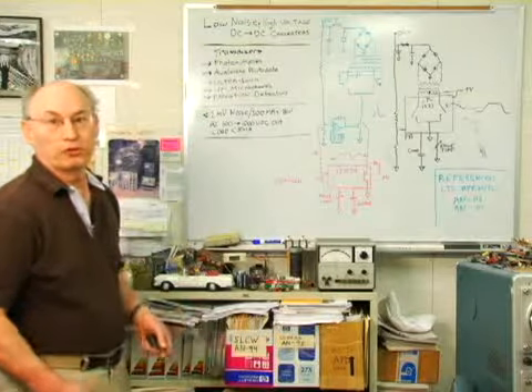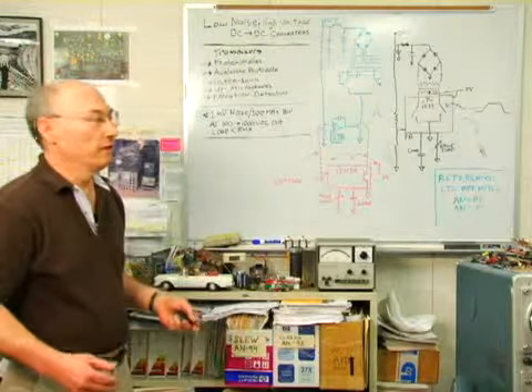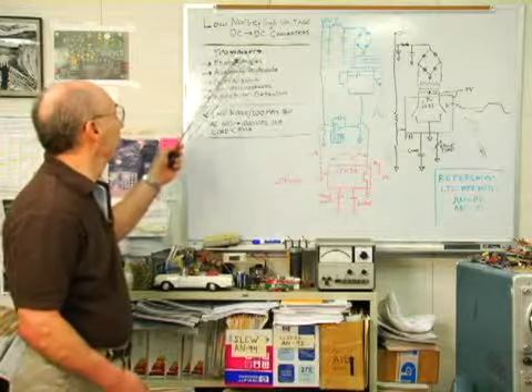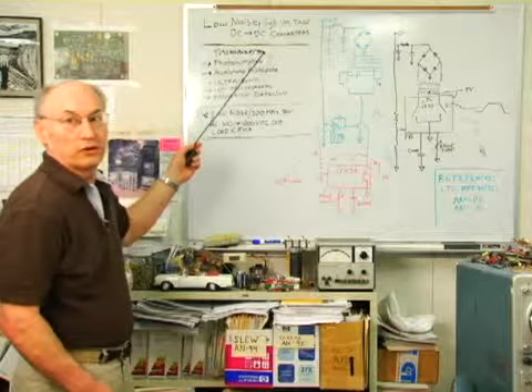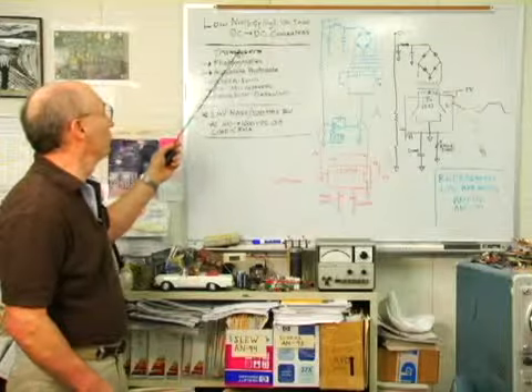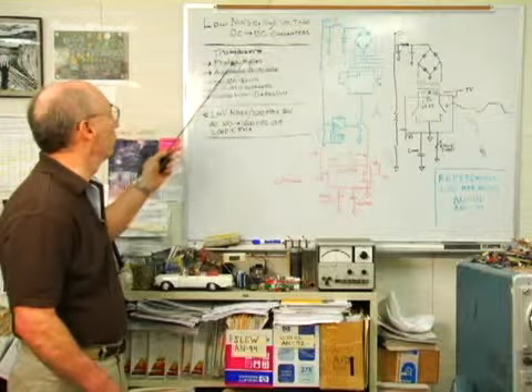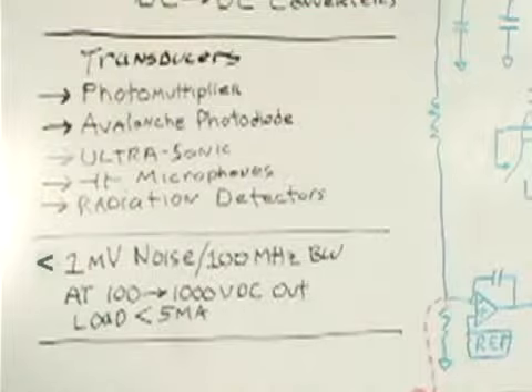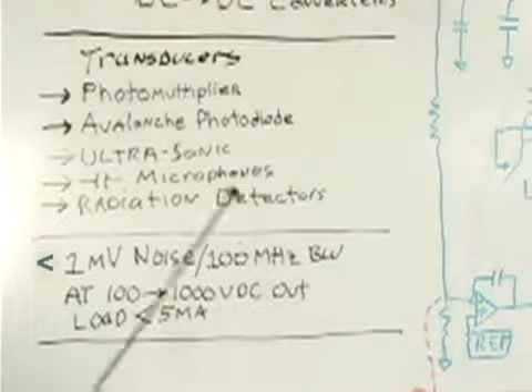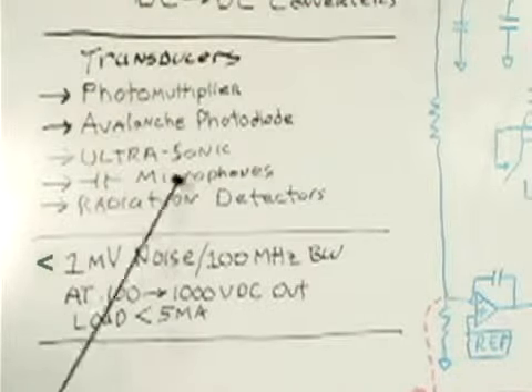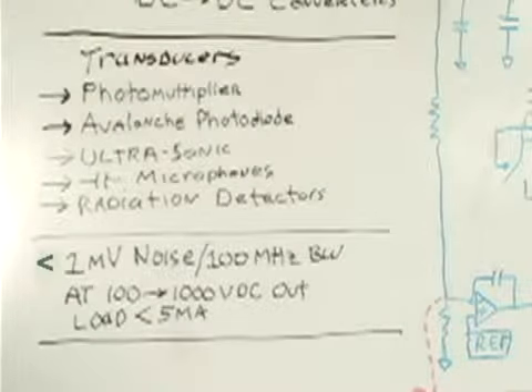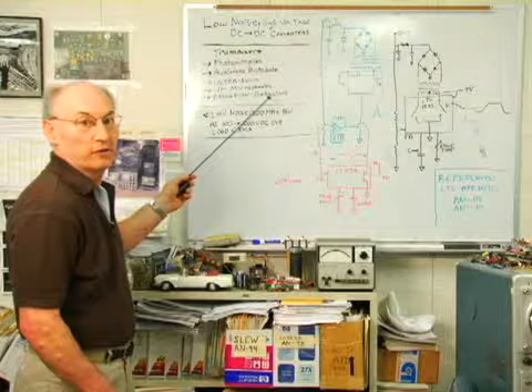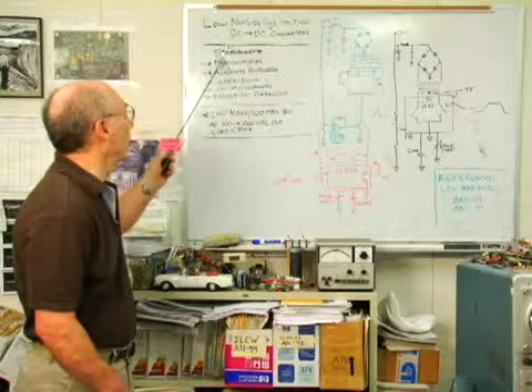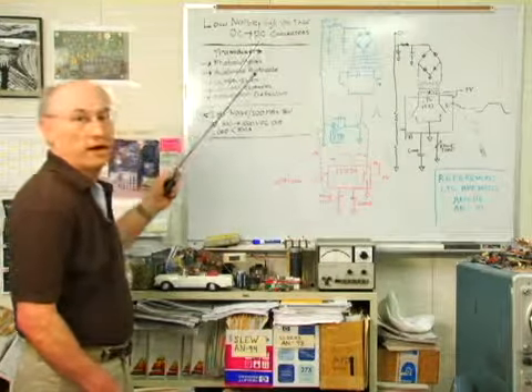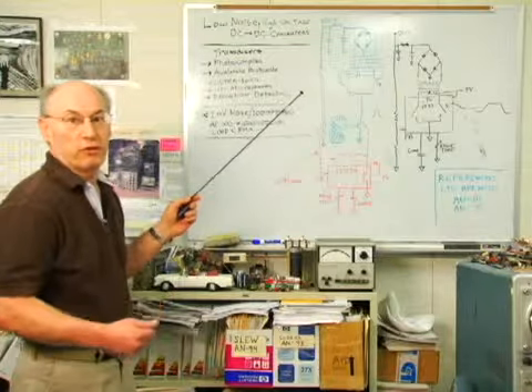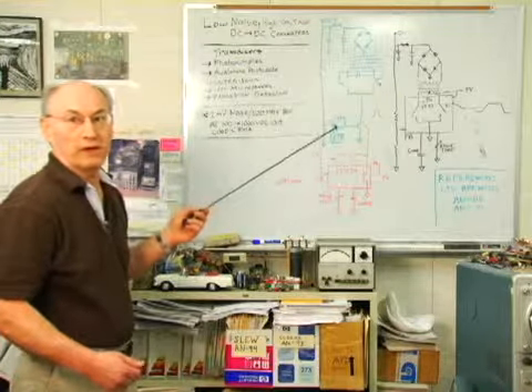A good question might be, who needs it? The answer is people doing primarily transducer signal conditioning. Transducers that need this low noise, high voltage include photomultipliers, avalanche photodiodes, ultrasonic transducers, capacitance microphones, and radiation detectors. These all require high voltage, and any noise on the high voltage can masquerade as false signal coming out of the transducer, so it's highly undesirable.